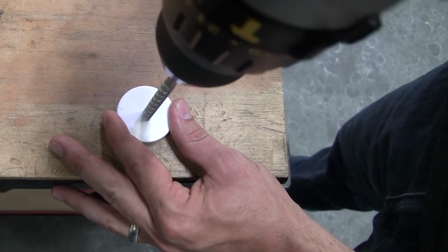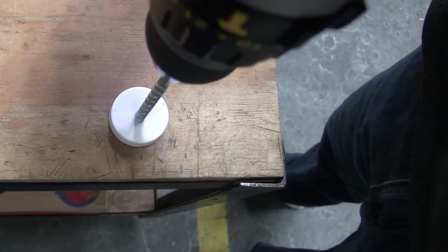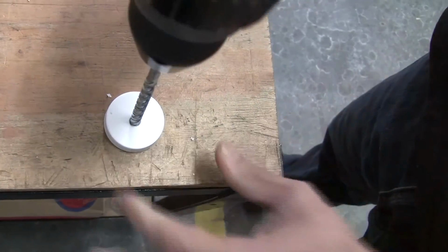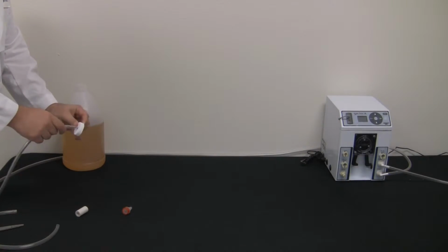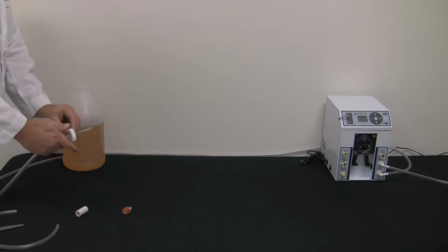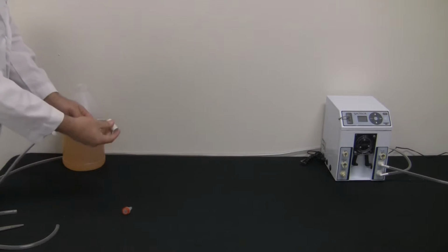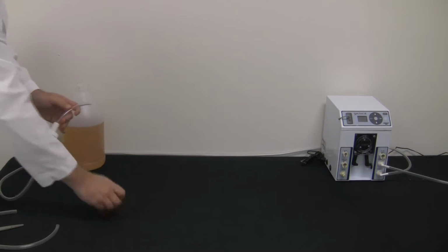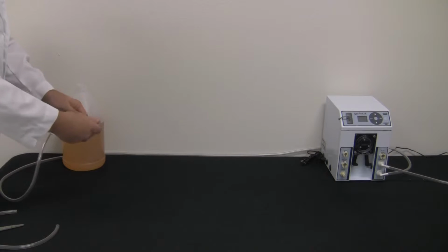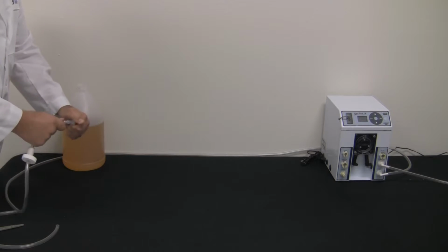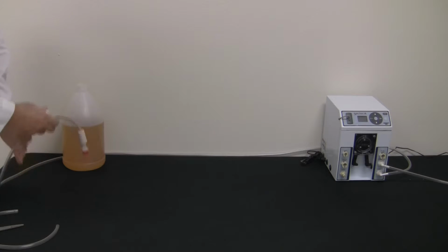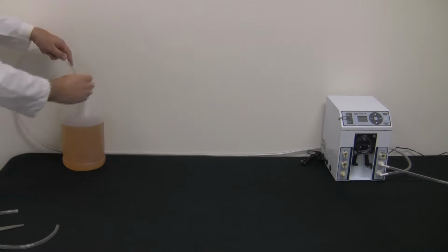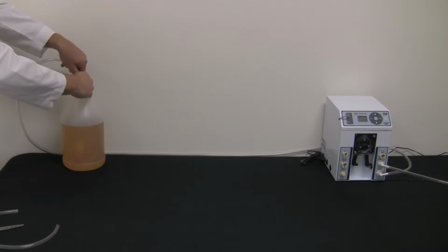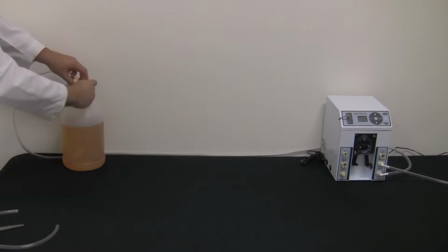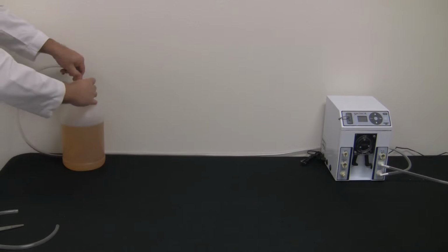Drill or cut a 3/8 inch hole into the cap of the detergent container. This will help keep the detergent suction tube from moving around. Insert the detergent suction tube through the hole of the cap. Slide the ceramic tube weight and umbrella foot valve onto the detergent suction tube. Place the cap on the detergent and push the suction tube to the bottom of the container. Be sure there are no kinks in the tube or obstructions that would impede the flow of detergent to the pump.